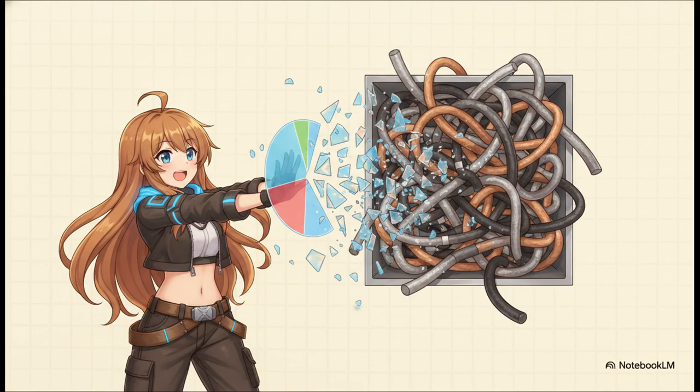But here is the crucial point, and a major exam trap. Examiners absolutely love to test the exceptions. That 40% fill rule does not apply if the raceway contains only these specific jacketed cables: mineral insulated, aluminum sheath, copper sheath, armored cable, or non-metallic sheath cable. Why is that? Well, because these are complete cable assemblies wrapped in their own protective jackets, which is totally different from pulling individual loose insulated conductors. So remember, if a question asks about the max fill for loose insulated wire, boom, it's 40%. But if you're only pulling armored cable in that raceway, the 40% rule is completely off the table.